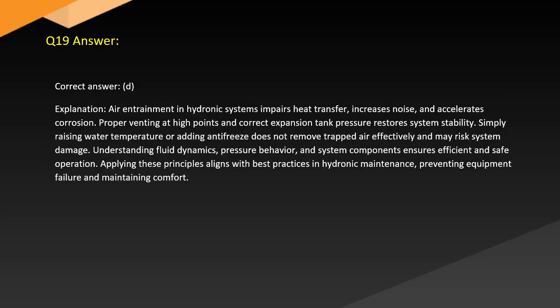Answer. Correct answer, D. Explanation. Air entrainment in hydronic systems impairs heat transfer, increases noise, and accelerates corrosion. Proper venting at high points and correct expansion tank pressure restores system stability. Simply raising water temperature or adding antifreeze does not remove trapped air effectively and may risk system damage. Understanding fluid dynamics, pressure behavior, and system components ensures efficient and safe operation. Applying these principles aligns with best practices in hydronic maintenance, preventing equipment failure and maintaining comfort.